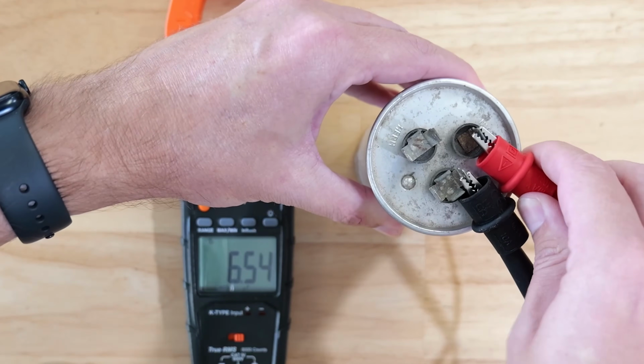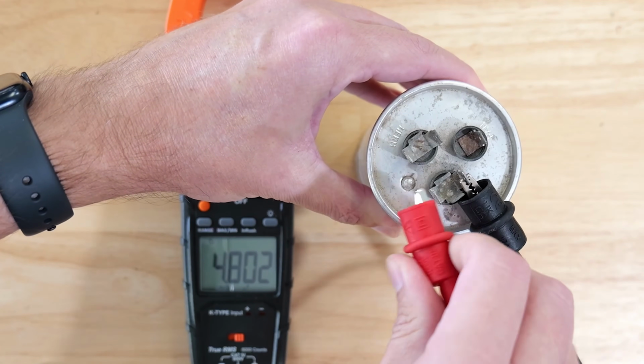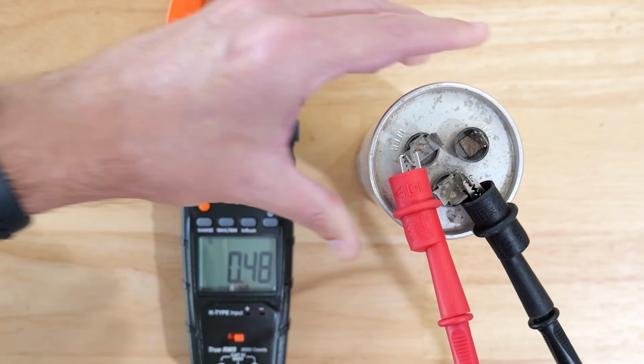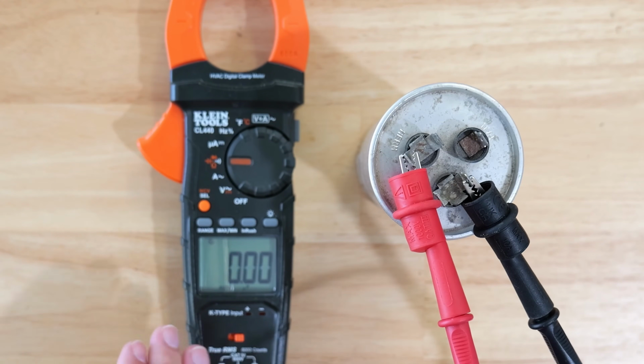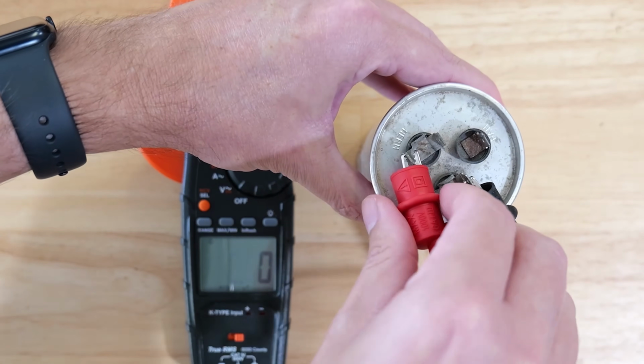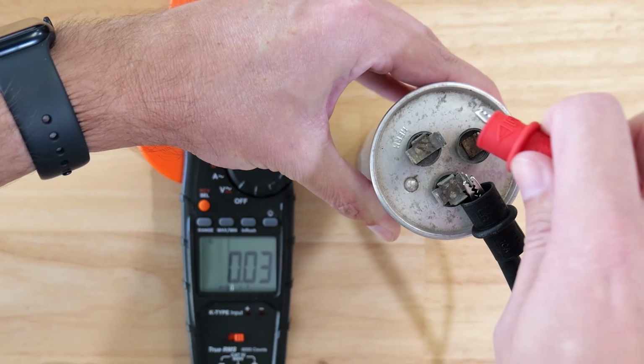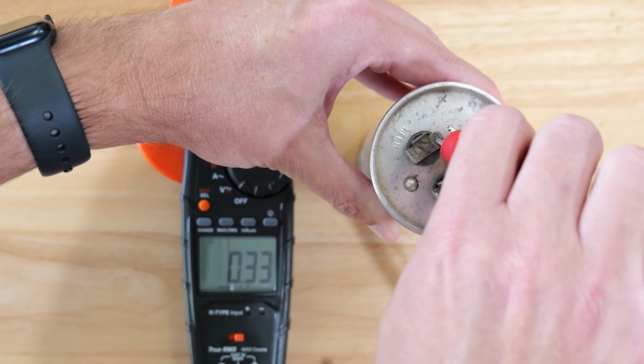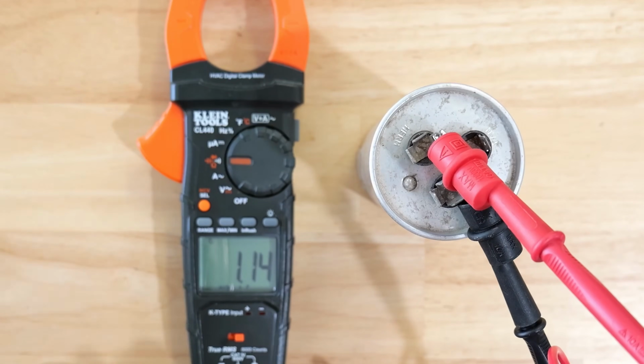But now let's check from the common, and then we're going to take this other probe that was on the fan, I'm going to put it on the hermetic terminal, and we're going to see what that reading is. All right, so as you can see, the multimeter is just jumping around. This is usually a really good indication that the capacitor is bad, but just to make sure it's not where I have my clip, I'm going to put it on one of the other terminals, see if we get a different reading, because that can sometimes be the case due to corrosion.